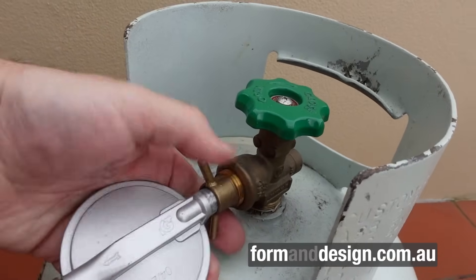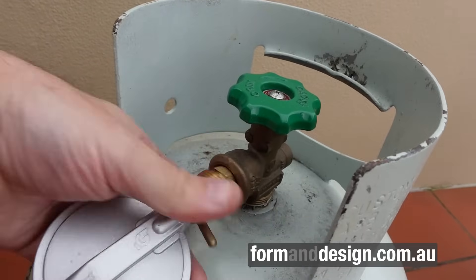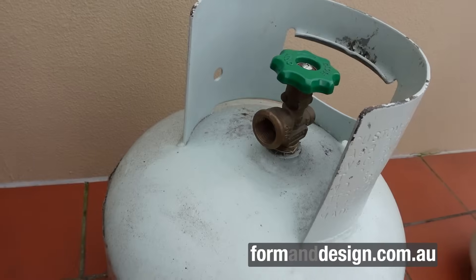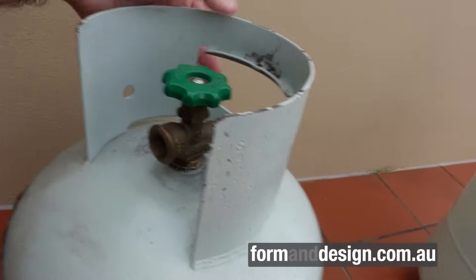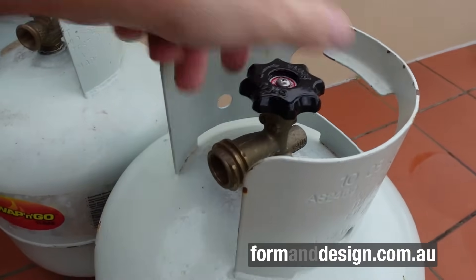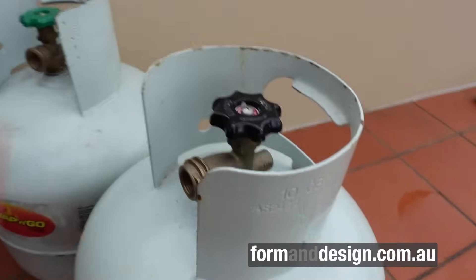One important thing about the old POL fitting: if you open the valve it releases gas — there's no safety mechanism to stop gas flowing out. The LCC 27 bottle is different and inherently safer. If you open the valve on an LCC 27 bottle, you can hear there's no gas coming out, so they're safe for transport and safe for storage.